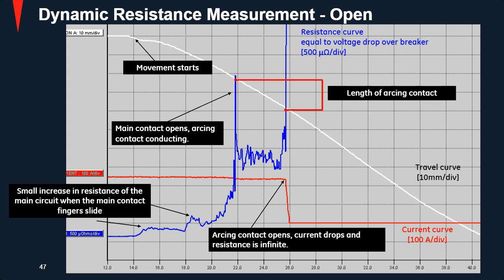Your right line right here is your travel line. So based off these 2 points on the line where they intersect, the distance between these two is the measurement of your arcing contact. That's how much arcing contact you have left. The general rule of thumb is if you lose more than 6 millimeters of your arcing contact, it needs to be replaced.